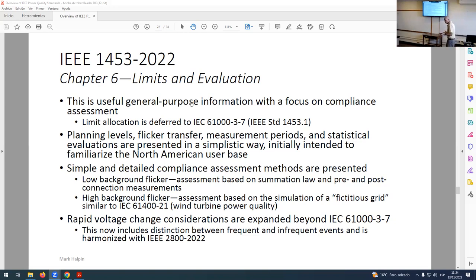And because of that inrush, we get so-called rapid voltage change. That doesn't happen often enough to produce light flicker, okay? But we don't want those kinds of regular large voltage changes. And that wasn't covered in the IEC, and it's still not. So one of the things that we put into 1453 is more guidance on how to manage that type of power quality issue, okay? Now, not only that, but because that was driven by our concern with interconnection of inverter-based resources like solar farms, IEEE 2800, which we're about to talk about, is our document for interconnecting IBR generating resources to the transmission, HV/EHV system. Okay, this is where it's a problem. So we made sure that what was in 1453 is consistent with 2800.